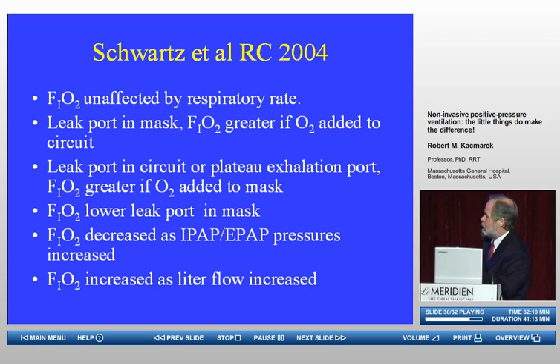The lowest FiO2, 22%. Leak port in the mask, O2 flow added to the system, 5 liters per minute, oxygen delivered into the mask. So you had the leak port in the mask, oxygen delivered into the mask, and the highest setting on the mechanical ventilator, virtually no oxygen delivered to the patient. Even when we dropped it to the lowest settings, we had minimal increase in the FiO2 with this type of configuration. The highest FiO2 was with the leak port in the circuit, high flow, 10 liters of oxygen into the mask itself, and the lowest setting on the BiPAP. In other words, 78%, a tremendous amount of variability, increasing to the highest settings on the ventilator, 40%.